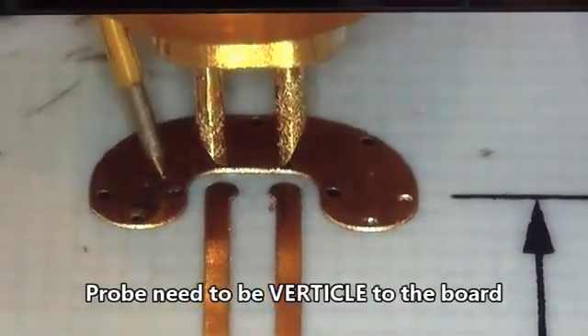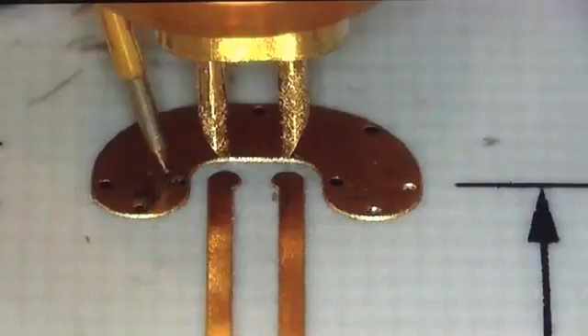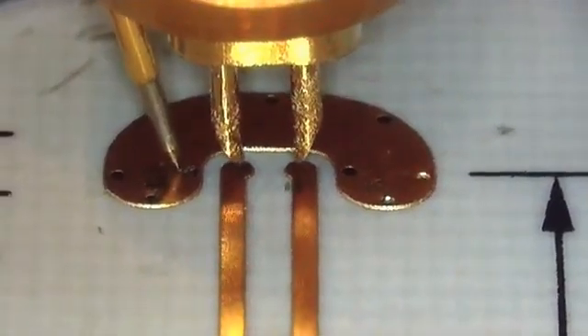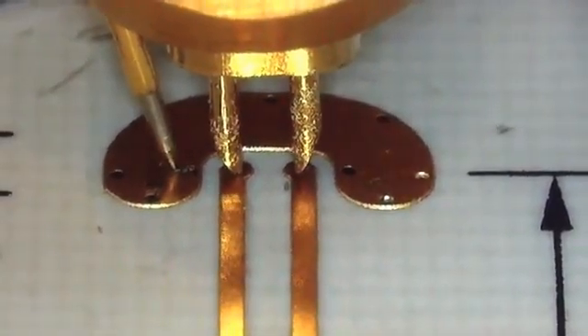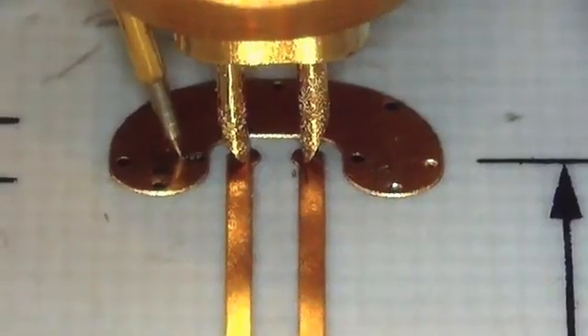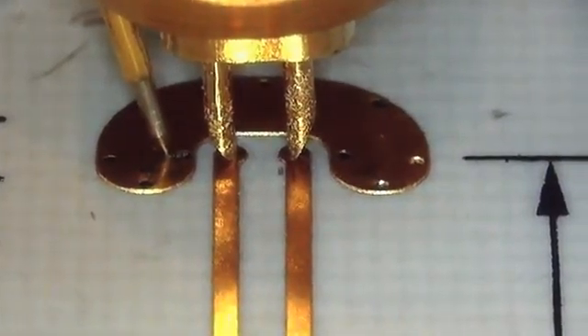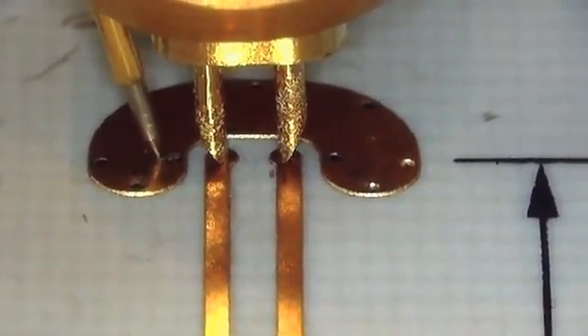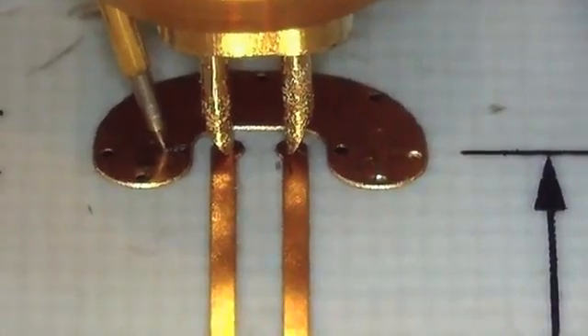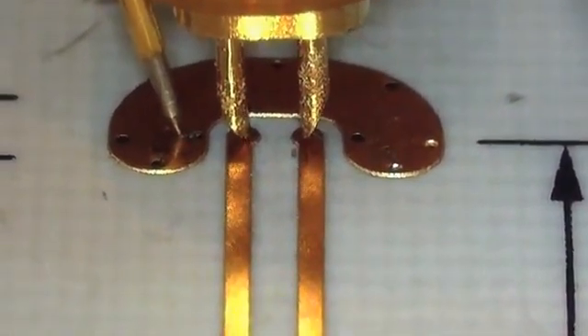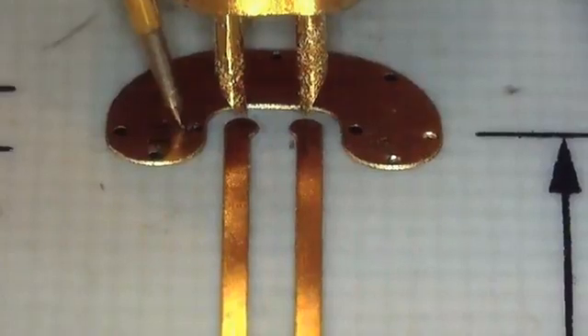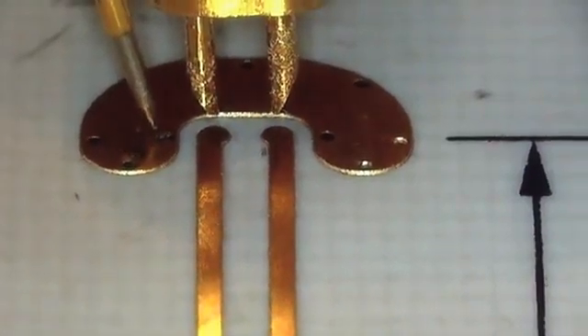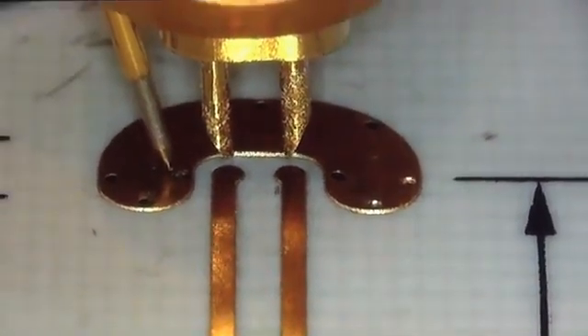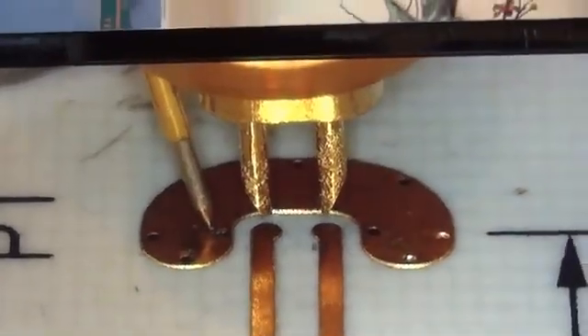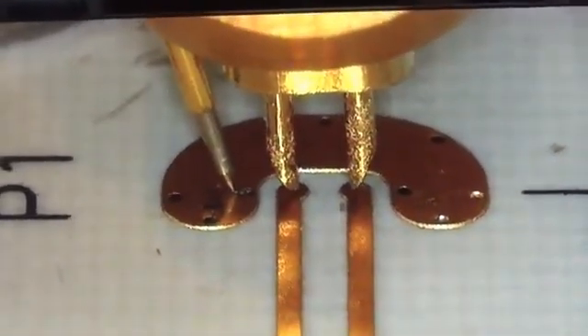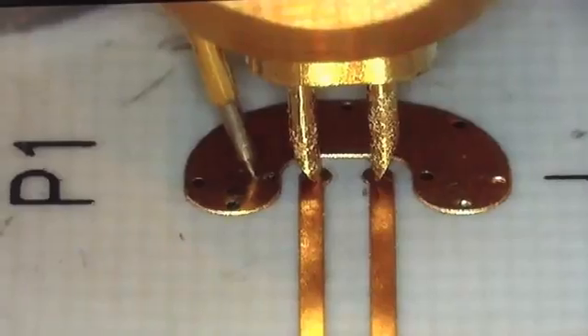You can see the silver pin that needs to be sliding into its sleeve. If it doesn't slide into the sleeve, it will bend and damage the ground. If it doesn't, what you want to do is adjust the probe so it's more vertical and retest it like this to make sure that the probe tip is in the sleeve.